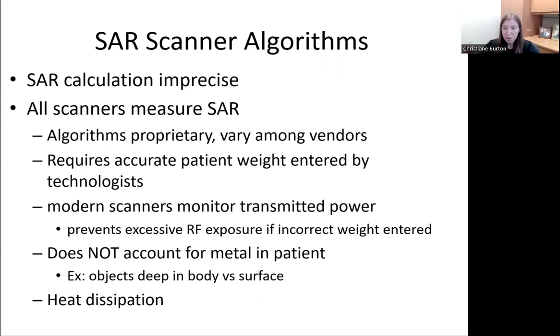Having said that, most modern scanners monitor transmitted power to prevent excessive RF exposure in case an incorrect patient weight has been entered. The scanner will estimate energy deposition for tissue. It won't account for any metal in the patient, which is much more efficient at absorbing RF energy, but it does matter where the metal is located in the body. So an aneurysm clip deep within the body won't have the same impact as if it were on the surface. Another example is plates in the femur will heat up because the femur isn't as deep in the body. Metal on the surface that isn't ferromagnetic, like tattoos, orthodontic work, makeup, etc., can also cause heating.